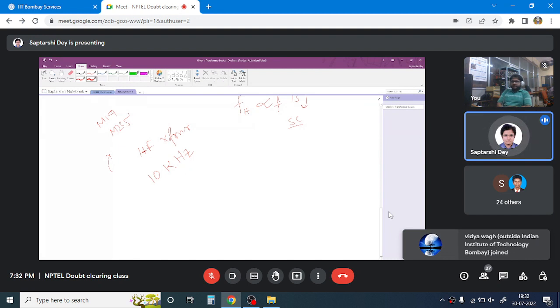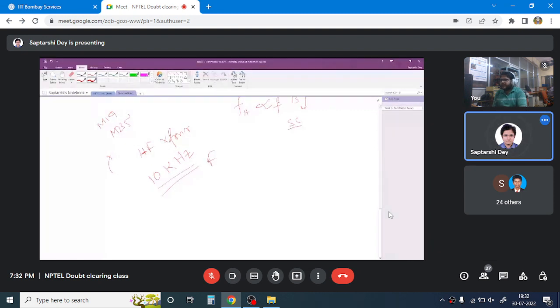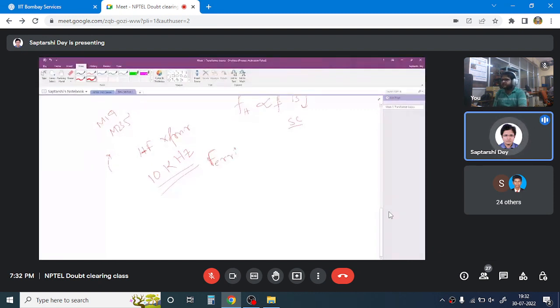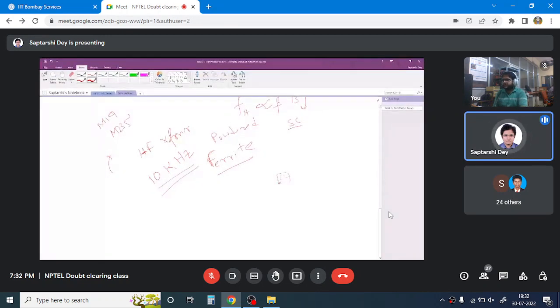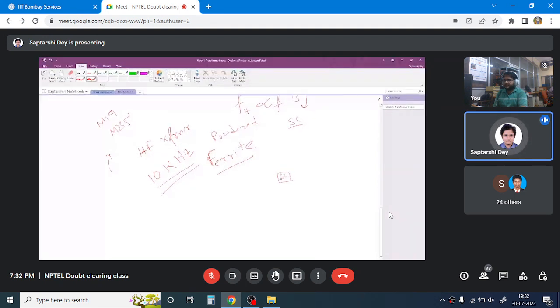Here the core loss is so high with this kind of electrical steel that it cannot be used. There might be some advanced materials nowadays, but conventionally what is used is powdered ferrite. So iron is powdered like this and pressed together. They are insulated, obviously, and pressed together. As a result, eddy current cannot flow in between them. Lamination does not work there. You have to powder them and press them together so that the eddy current is very, very less. This is done to reduce the core loss in very high frequency transformers that work in tens or hundreds of kilohertz. But don't be confused, the theory of the transformer is the same. That does not change.